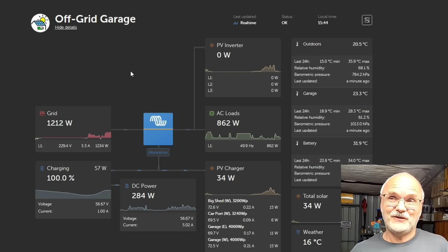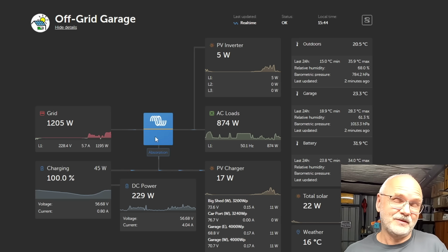Well, guys, so far this failed experiment from today. Please leave your comments down below. What do you expect? What is going to happen? The Multiplus is trying to turn off our PV inverter because our battery is full by increasing the frequency. But it cannot increase the frequency because there's an AC in signal. Will either the Multiplus shut off completely because of a high voltage spike on the output? Or will the PV inverter shut down for the same reason?